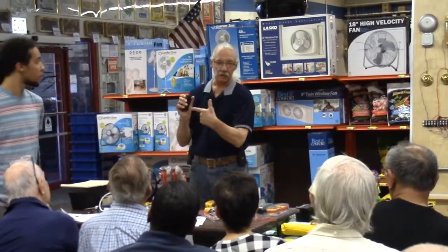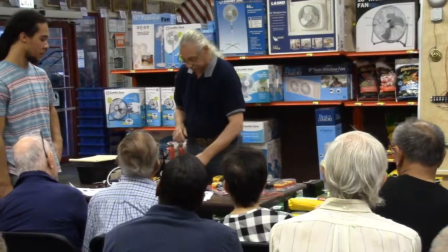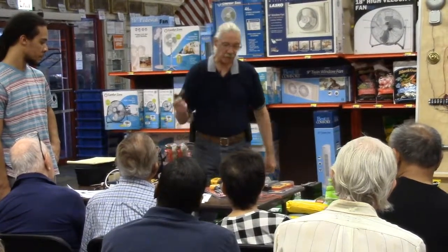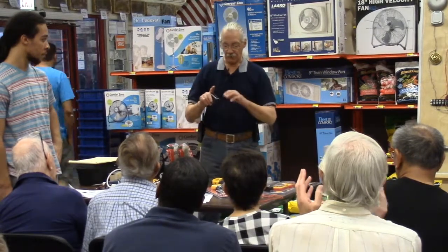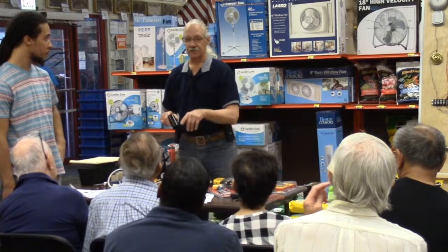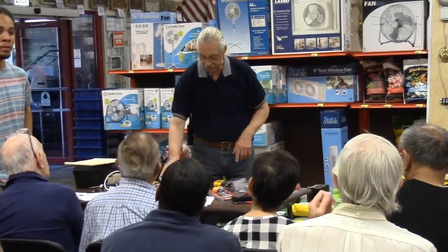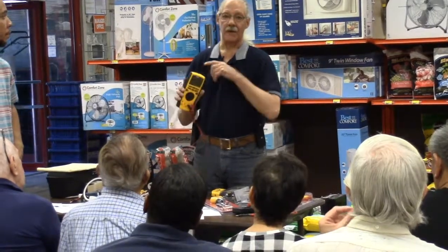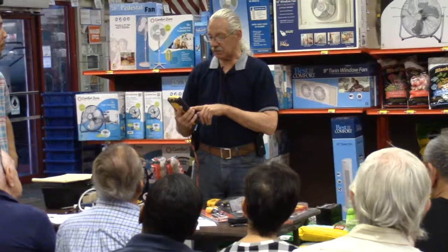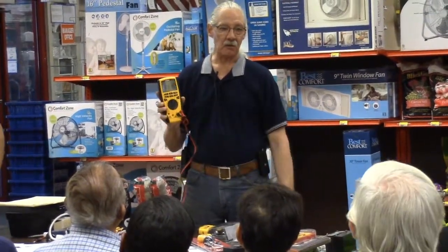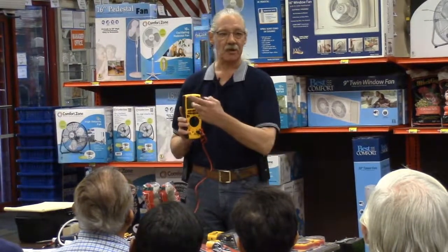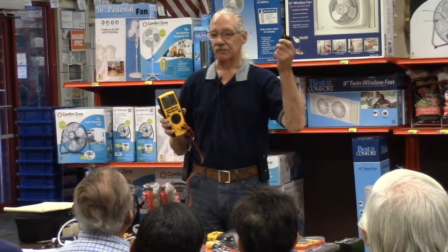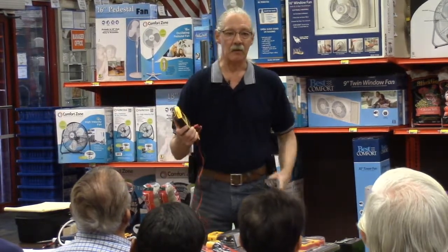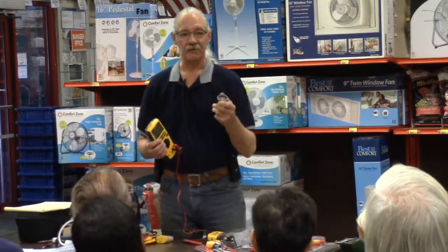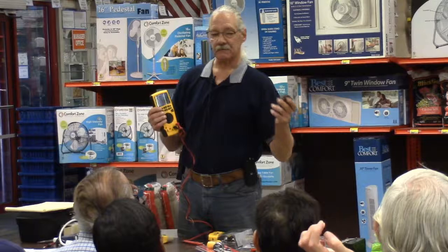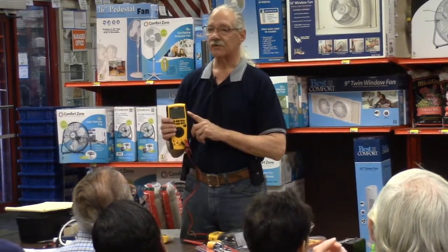If I got an OL, it would mean one of two things. Either the capacitor was bad or the capacitor was over the range of the meter. So when you're measuring capacitance, you have to know the range of the meter. If my meter was only capable of reading up to 400 picofarads and this was a 450, it would just come OL with no reading, and I may assume that this is bad, but the meter couldn't read it. Okay, it couldn't induce enough voltage, where I could read this capacitor. So when you're getting into the more sophisticated tests, you have to also know the ranges of your meter.